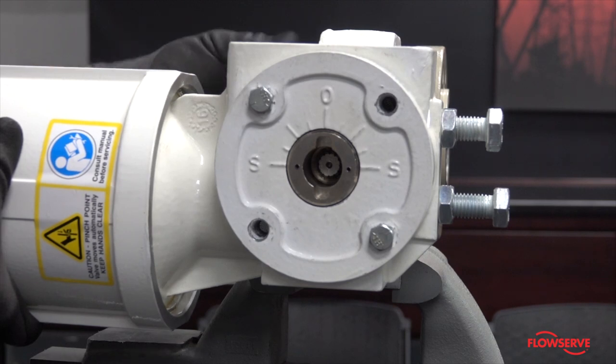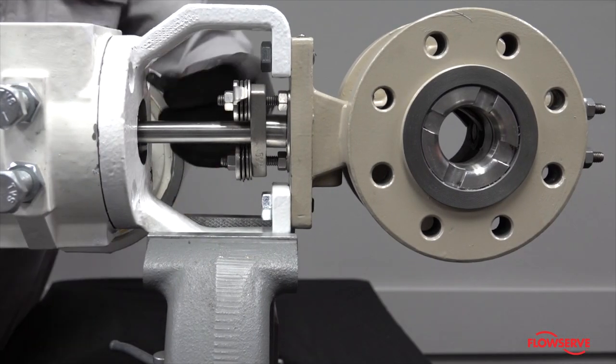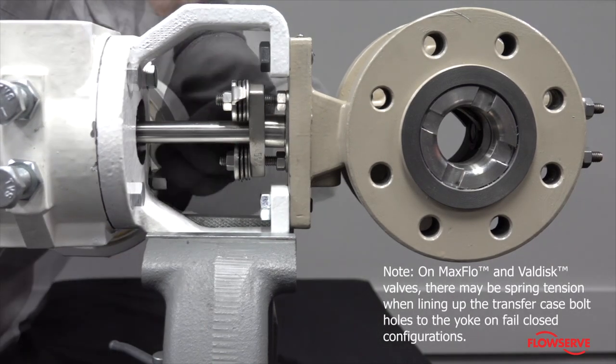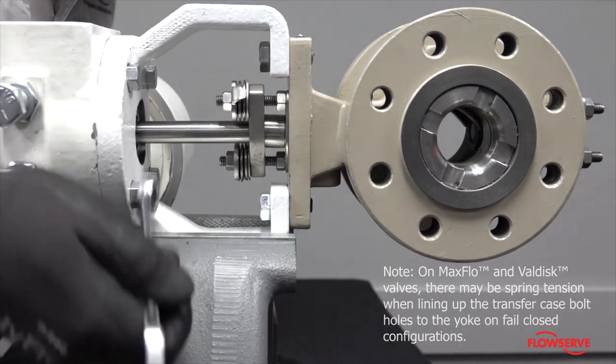The line on the end of the shaft should be in the same orientation as noted previously. Reinstall the four tapered bolts. Note: on MaxFlo and Valdisk valves, there may be spring tension when lining up the transfer case bolt holes to the yoke on fail closed configurations.